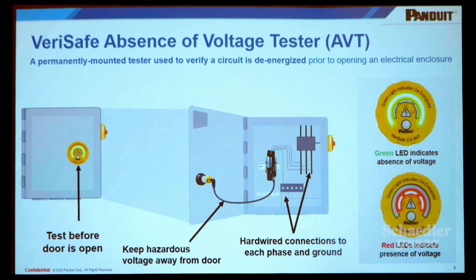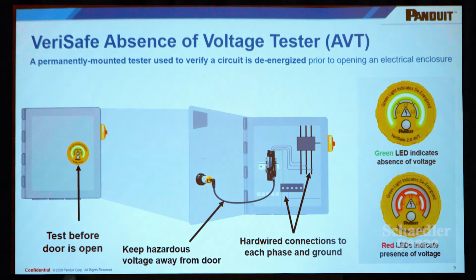This is basically the system, how it's designed. So again, the indicator module is tested at the door itself. Again, it keeps hazardous voltages off of the door, which is a huge advantage over some other devices out there for testing at the panel door. And then you have the isolation module mounted at the back. You can also have dry contacts coming off of here, so you can do some other integration like additional lights, or at the booth we have one that has an electronic interlock hooked up to it, so when I hit the button, the door pops open. All right, you can get into some pretty interesting integrations with an AVT.